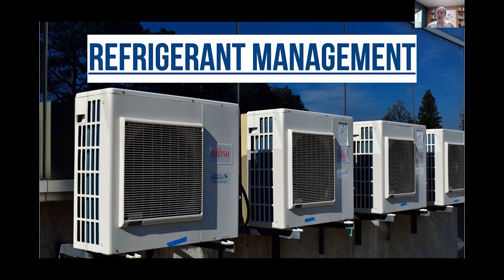We're gonna need more air conditioning because of climate change. And we're also deploying heat pumps as a climate solution. And with that, we've associated a lot of refrigerant. And if you're using any refrigerant that has more of a global warming potential than CO2, it's a really big deal that it doesn't make it out into the atmosphere. So the big ways to do this, right, are lower the demand, lower the use of these kind of appliances, replace the refrigerants with low global warming potential refrigerants. So you can ask for low GWP options, increasing efficiency when you are doing refrigeration, controlling leakage, and ensuring recovery and reclamation and proper destruction. You can check the US EPA if you're in the US for how to do that at the end of life.